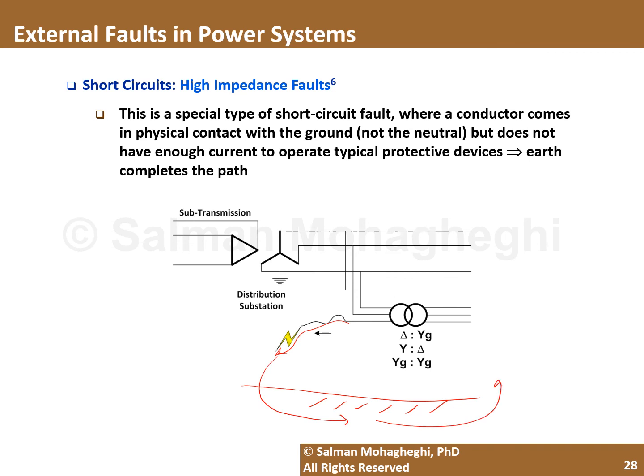This in particular is problematic if you have a transformer with, for example, a delta configuration or a grounded Y. Imagine this scenario here. If you have this line which is opened and hits the ground, if on the low voltage side you had a YY transformer which was not grounded on either side, then you wouldn't have any currents. But because, for example, in this scenario, you have either a delta Y transformer or a Y delta or grounded Y to grounded Y, through the low voltage side, you might actually start feeding the fault, and this is known as the backfeed problem. That is sometimes common in high impedance faults.